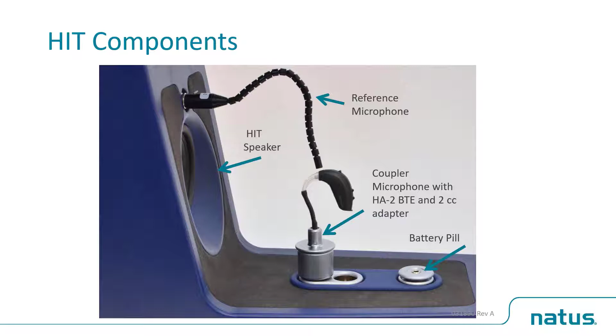And then the coupler mic, which you can't see because it's down into there, is taking the place of basically the probe tube. And then you are going to attach the hearing aid to that coupler via a hearing aid coupler adapter. And that coupler adapter will be different whether you're using a traditional ear hook BTE or if you're using a RIC or a custom hearing aid. And then if you do want to test things like battery drain, there is a spot to plug in battery pills.